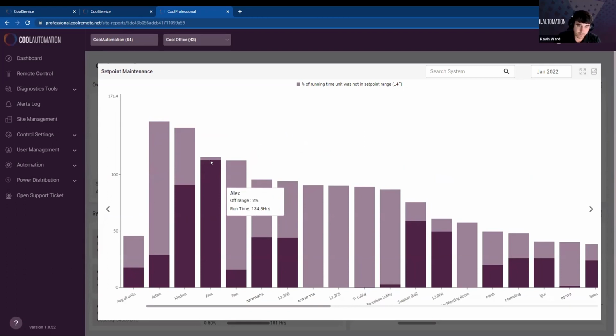With the full bar graph here, you can easily tell which fan coils are satisfying the space and how often they're out of range. This fan coil is working exceptionally well, satisfying it 98% of the time. It's only out of range 2%. Whereas the next group of fan coils here are never satisfying the space, indicating a potential issue or potentially a set point that is unrealistic for that fan coil to actually satisfy. Perhaps they're set to 68, but the system's only able to hold 72. Or in heating mode, if they're set to 90, it's too cold outside and it's unrealistic for the set point to actually ever be satisfied by the system.